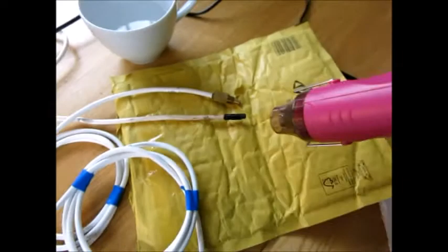And what I'm going to do is warm this up with this hairdryer to simulate the boiler actually putting heat into the system. And I'm going to warm the plate heat exchanger one up as well at the same time. And we'll see that this will start to climb up. There we go, 20. When it gets to the right temperature, about 70 odd degrees, 75 I think it is, the boiler will go out, but the boiler pump will keep running. I'll explain about that in a second.